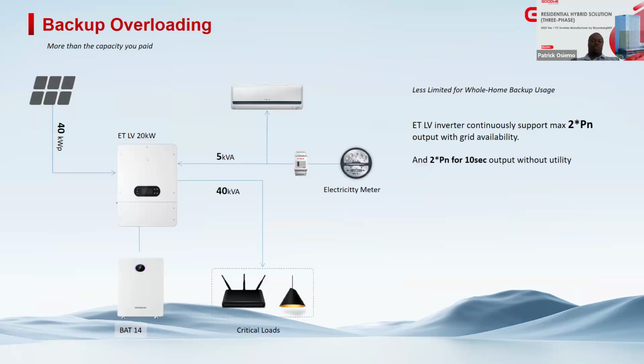Then we have the backup overloading. This is a key feature that takes two matters. If you have a house that now gets to consume a lot of constant load, the 20 kilowatt inverter, whenever the grid is connected, can allow continuous support of 40 kilowatt to the backup loads continuously if the grid is available.